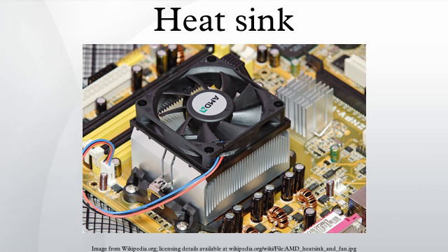To decrease the spreading resistance in the base of a heat sink, increase the base thickness, choose a different material with better thermal conductivity, or use a vapor chamber or heat pipe in the heat sink base. Optimization. Because fins are used to improve heat transfer, it is important to allow open spaces toward optimization. In other words, the shape of fins must be optimized such that the heat transfer density is maximized when the space and the materials used for the fin surfaces are constraints.